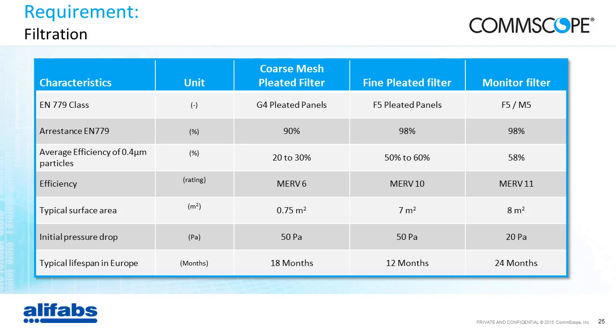So, a bit of a comparison between the filters that are being used in the free cooling industry now. And the one we use is the one in the column on the right. And you can see, by reaching F5/M5 and the efficiency that it reaches, it can be used on very critical sites. The other beauty of the filter we use, and again, let me highlight that it's a unique filter. We are the only ones to use this type of filter in the industry.